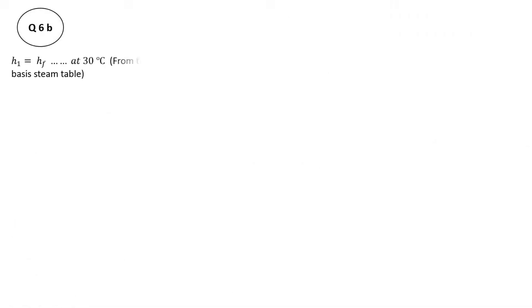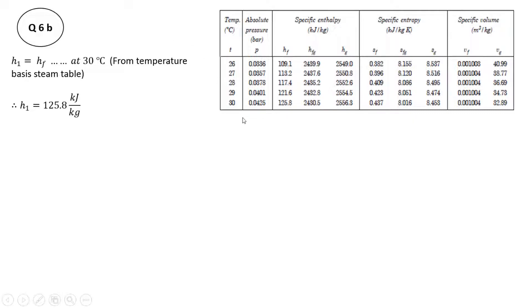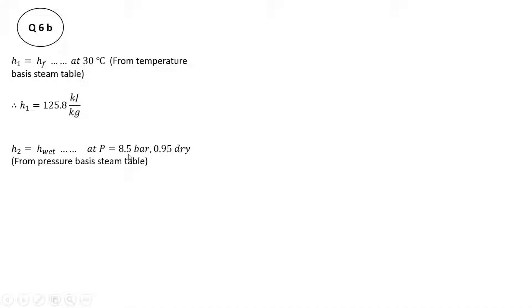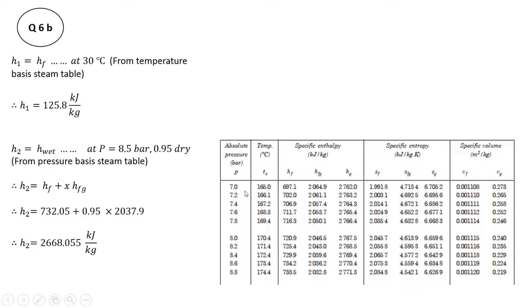Since feed water is supplied at 30 degrees centigrade, H1 is the specific enthalpy of saturated water (HF) at 30 degrees centigrade from the temperature-basis steam table. At 30 degrees centigrade, HF is 125.8 kJ per kg. H2 equals H-wet because steam is generated at 8.5 bar with a dryness fraction of 0.95. Since dryness fraction is given, it is wet steam, so we use the pressure-basis steam table to find HF and HFG at 8.5 bar.